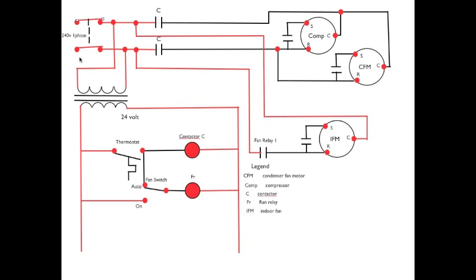Okay, the only thing we've done here is we closed the system switch. I want to notice this is 240 volts, so we have a two-pole switch and of course you're connected together. That's why the dotted lines are there. Now that's going to feed power to all different areas here and I'll go over that when we sequence it, but it's also feeding power to the 24 volt and making it ready to operate.